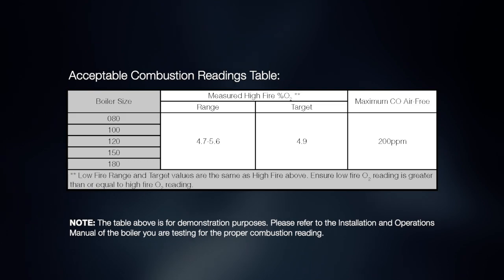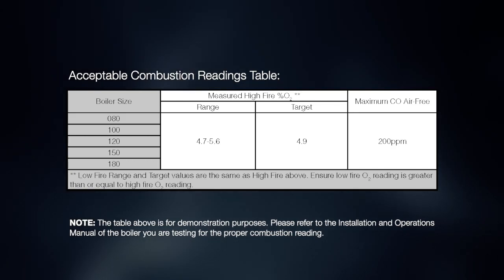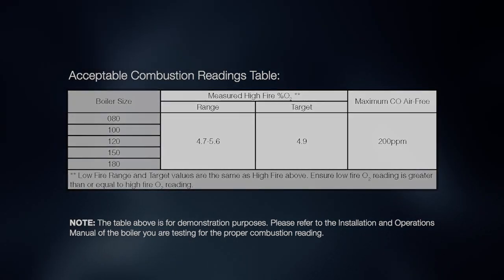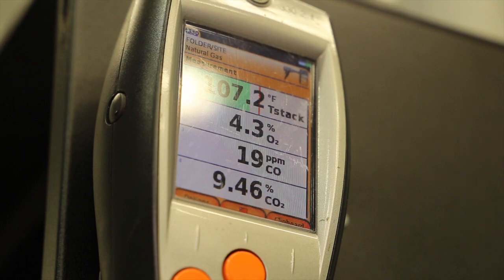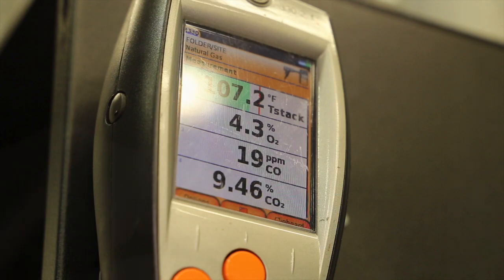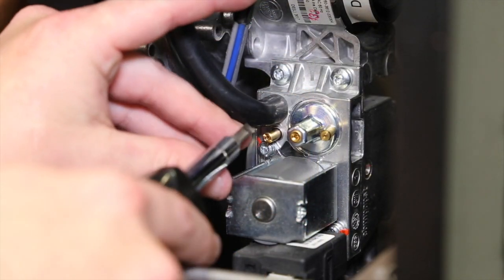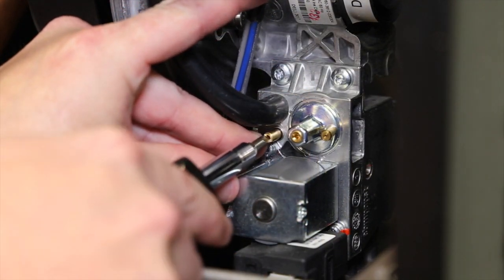Refer to the acceptable combustion readings table inside the installation and operations manual of the boiler you are servicing for the proper oxygen reading. If the oxygen level is not within the specified range, an adjustment to the gas valve throttle may be necessary.